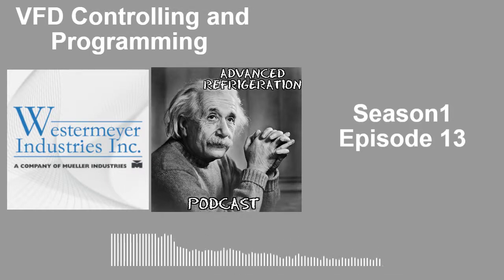On the Bitzers, I'll go through one frequency at a time. It may take me an hour to do a compressor, but say at 47.5 hertz it starts vibrating and making noise until 48.3 hertz. I'll take that frequency range out of the drive. You can go in the drive and tell it to skip that, and it'll skip that frequency when it's maintaining. It's great. It instantly stops the problem if you don't have one out of phase, and it's an easy way to stop issues like that.